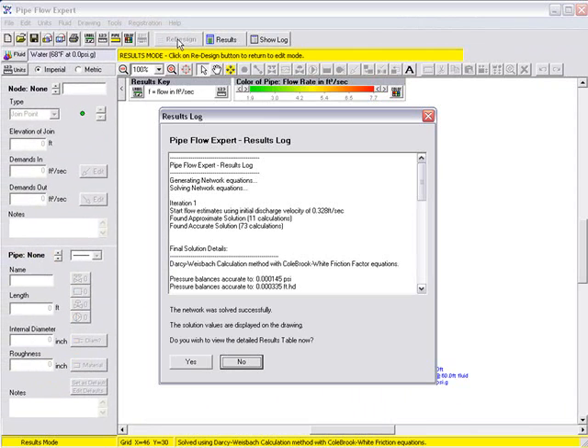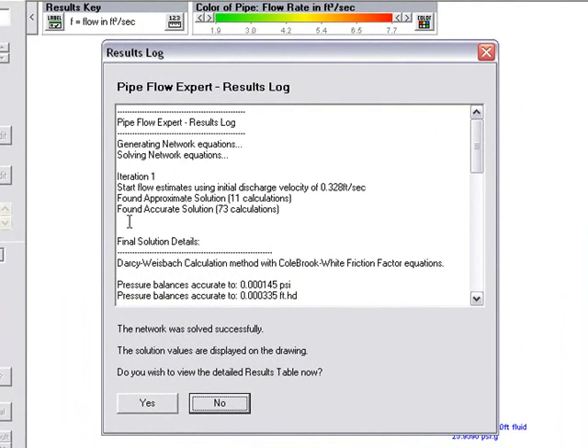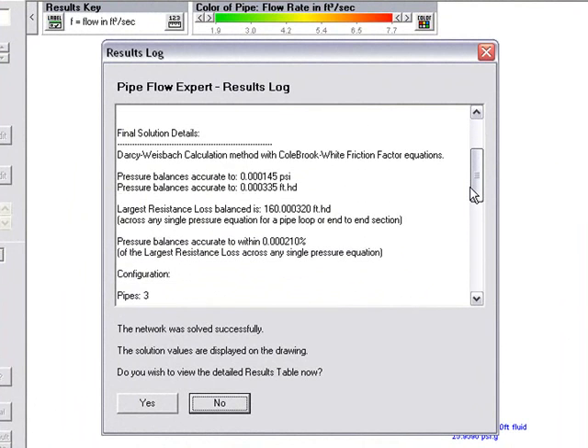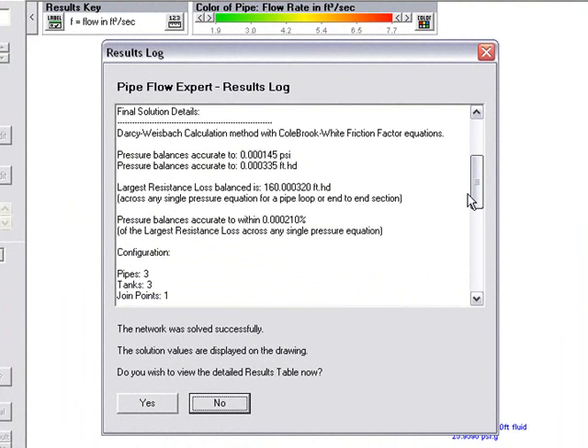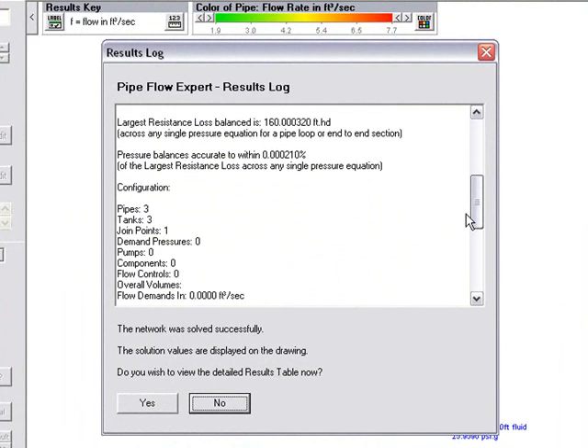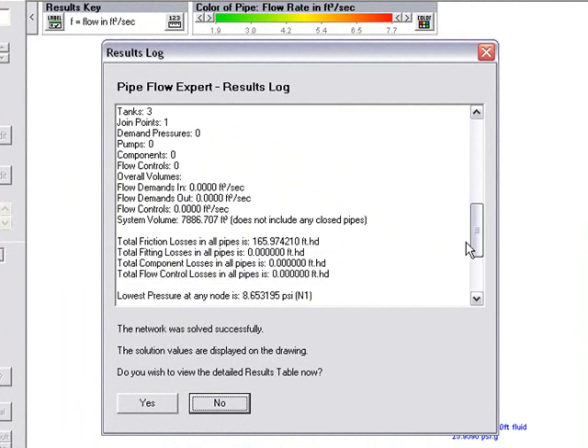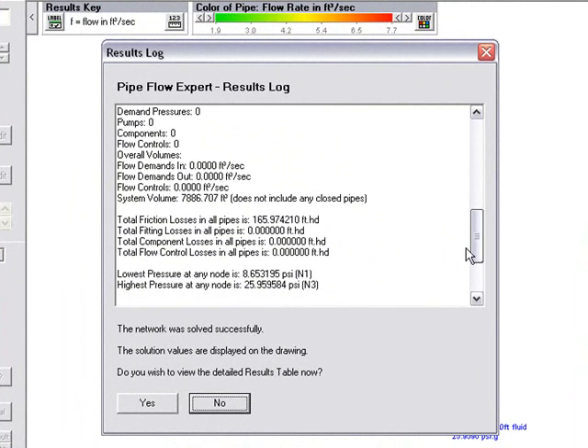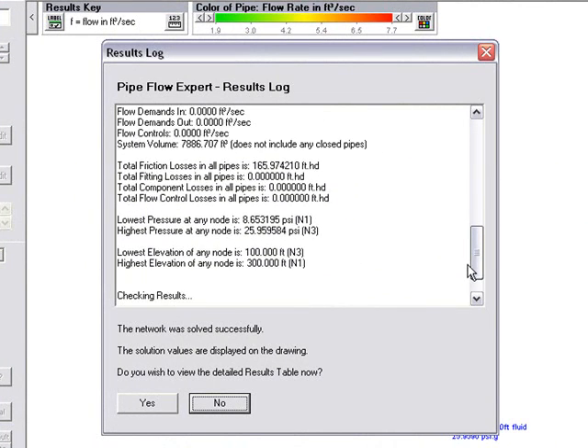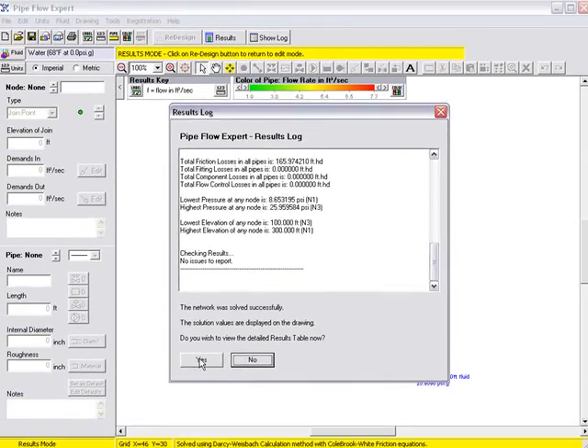We click calculate and the results log is now shown and we are told some information that says an accurate solution was found and it gives us some information to say the Darcy-Weisbach calculation method was used. And if we scroll the log down we can find information about the pressure balance accuracy and the number of pipes, number of tanks, total friction losses, etc. No issues to report and we are asked do you wish to view the detailed results table.